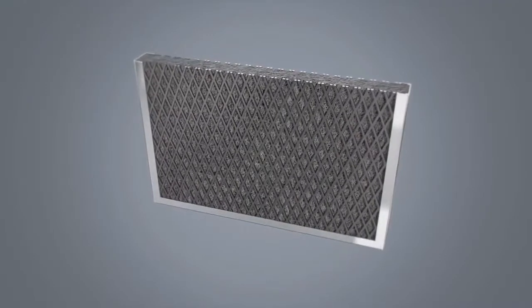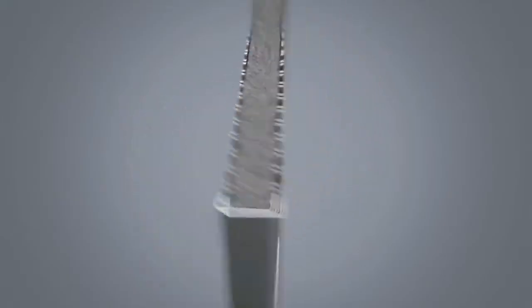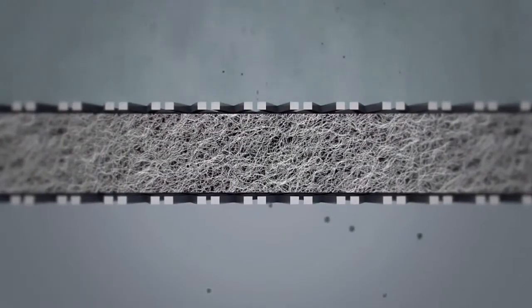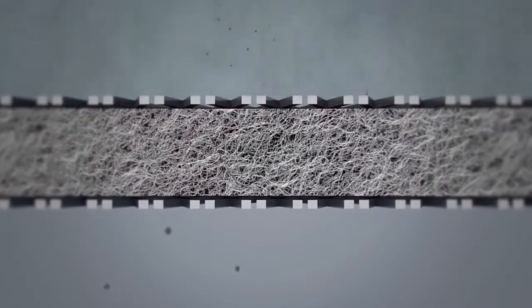In the next stage, the air passes through a packed bed of very fine stainless steel fibers. The microscopic coolant that remains in the air stream are accumulated into fewer but larger droplets.